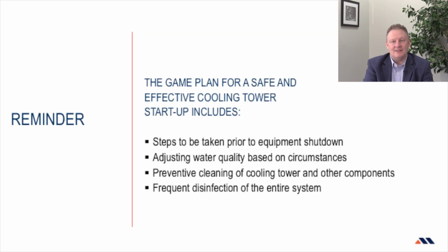To ensure a safe and effective cooling tower startup, a proper game plan must be established. This game plan must include specific interventions such as the initial steps to be taken before shutting down the equipment, adjusting the water quality based on the situation, the preventative cleaning of the cooling tower and its components, and the preventative disinfection of the entire system on a regular basis.